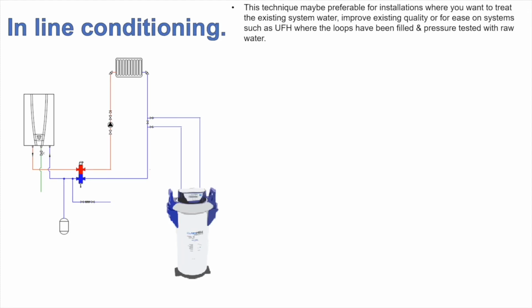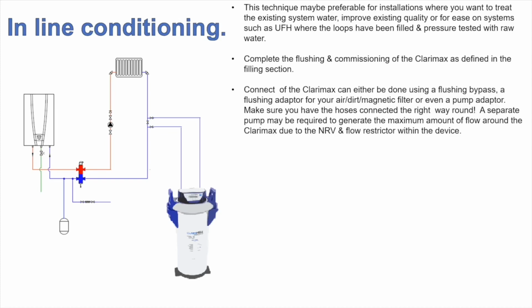Inline treatment. This technique may be preferable for installations where you want to treat the existing system water, improve existing quality for ease of systems such as underfloor heating, where the loops have been filled and pressure tested with raw water. Complete the flushing and commissioning of the Clarimax as we've done in the video. Connection of the Clarimax can either be done using a flushing bypass, a flushing adapter for your air, dirt or magnetic filter, or even a pump adapter. Make sure you have the hoses connected the right way around. A separate pump may be required to generate a maximum amount of flow around the Clarimax due to the non-return valve and flow restrictor within the device.